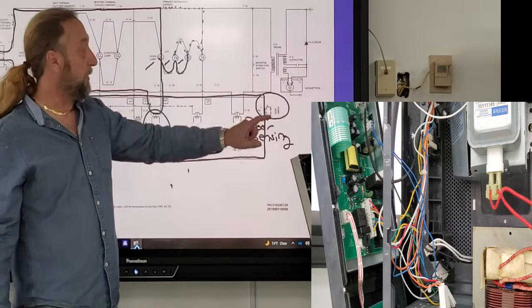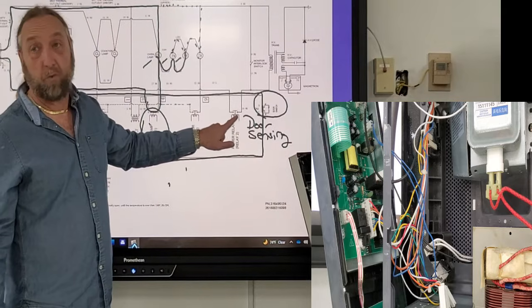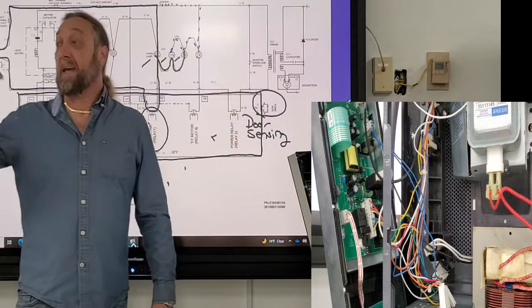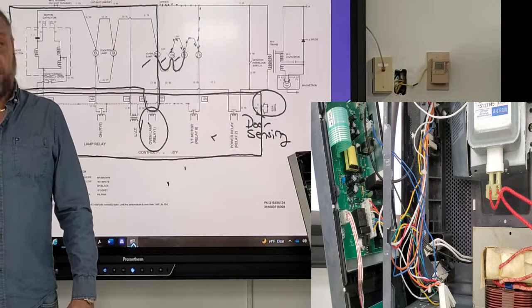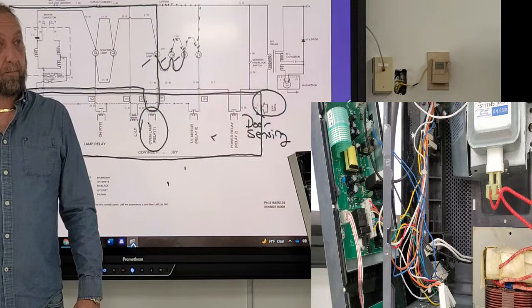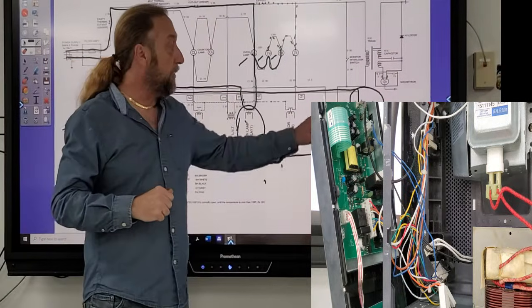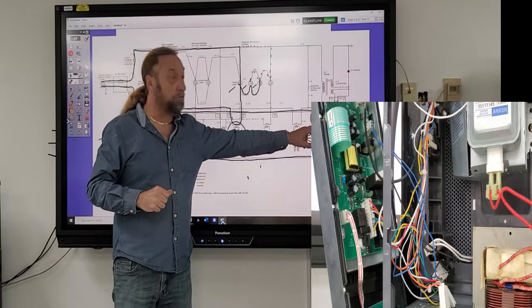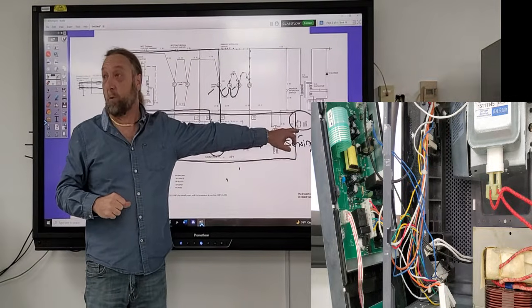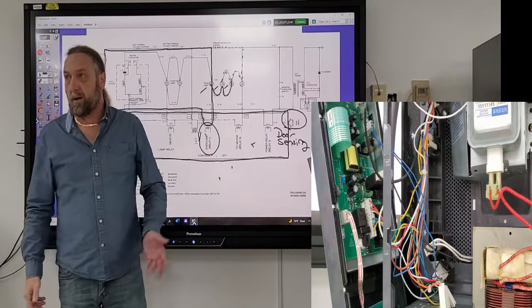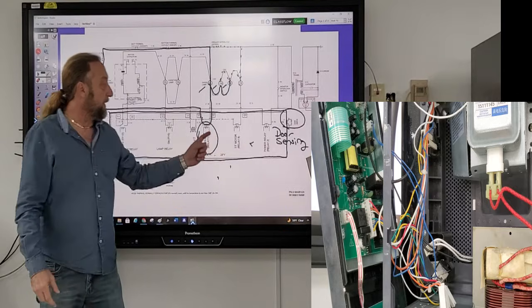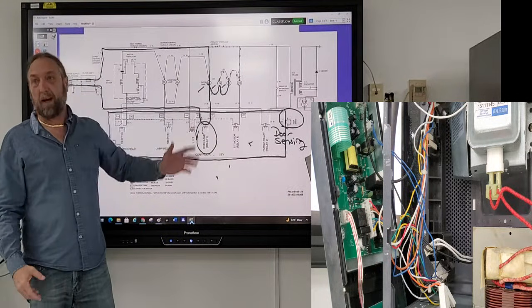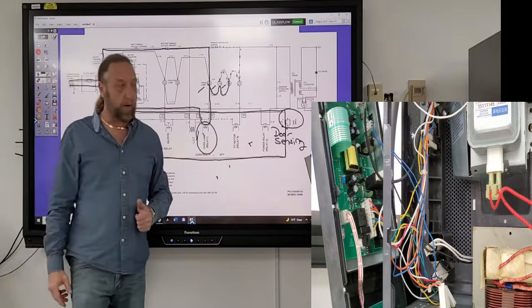I'll do it one more time for you to listen, because this relay will only close if I tell the board to run. Okay? So this will not close because it sees this door switch open. It will not let it run. But when this door is open, it closes this one trying to turn the light on, but that light's turning on other things as well.